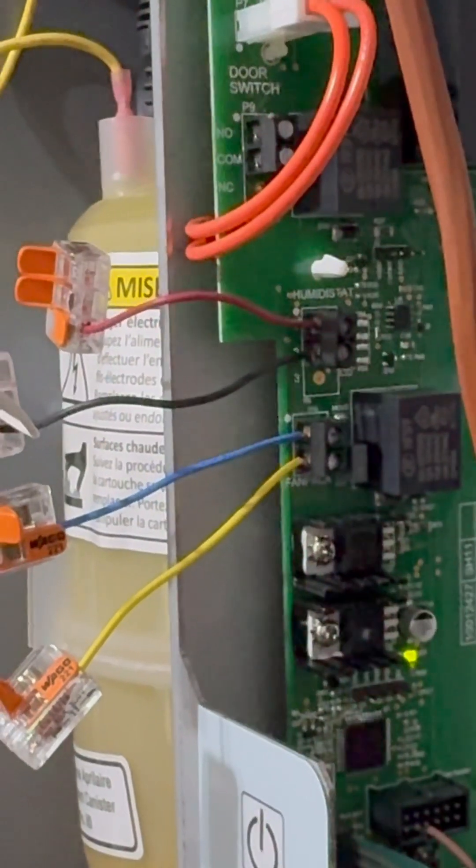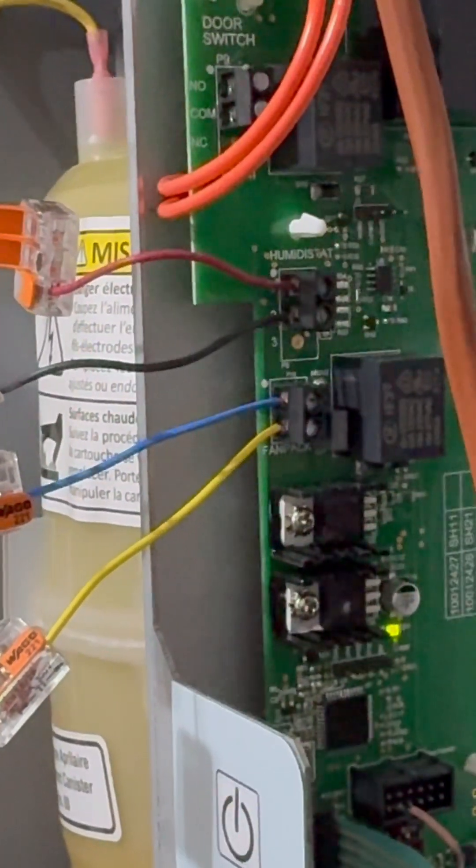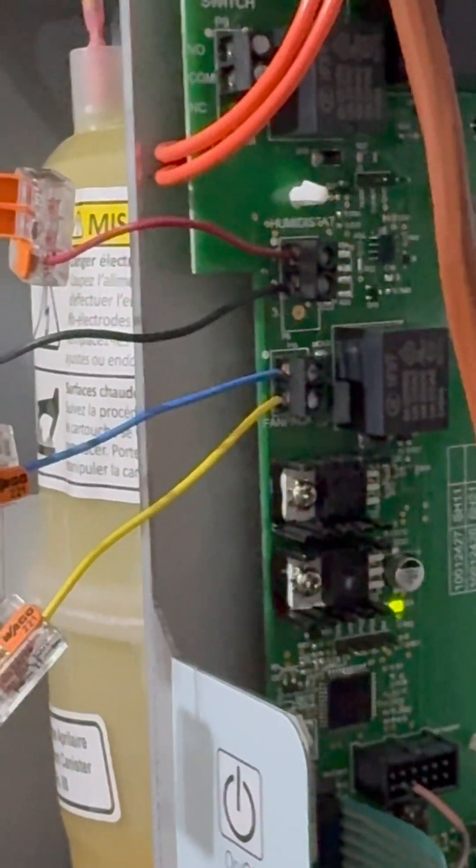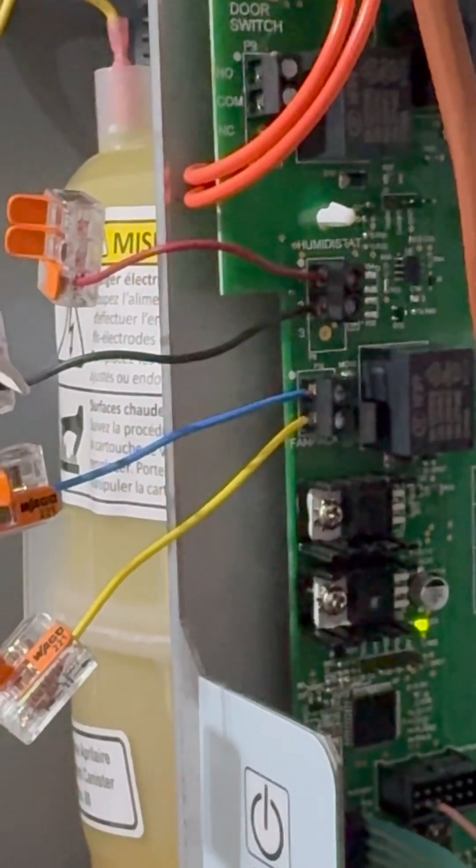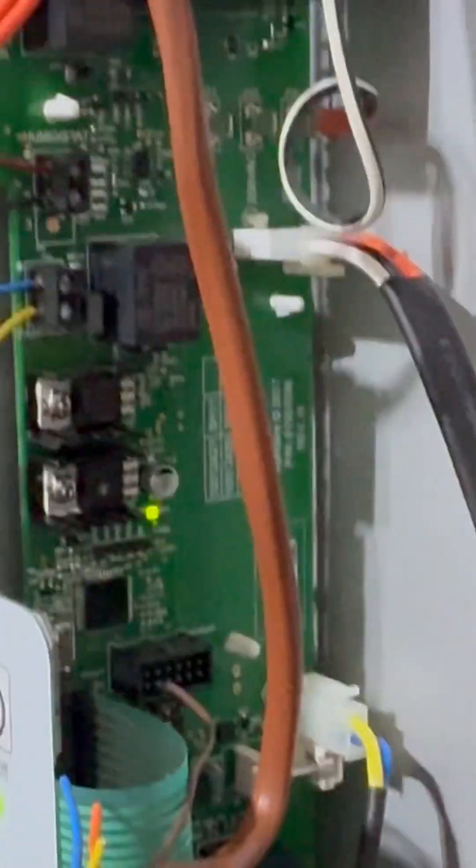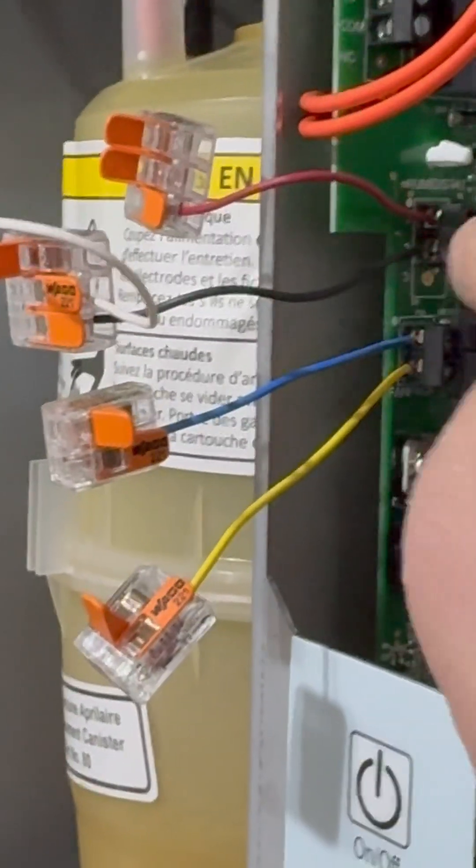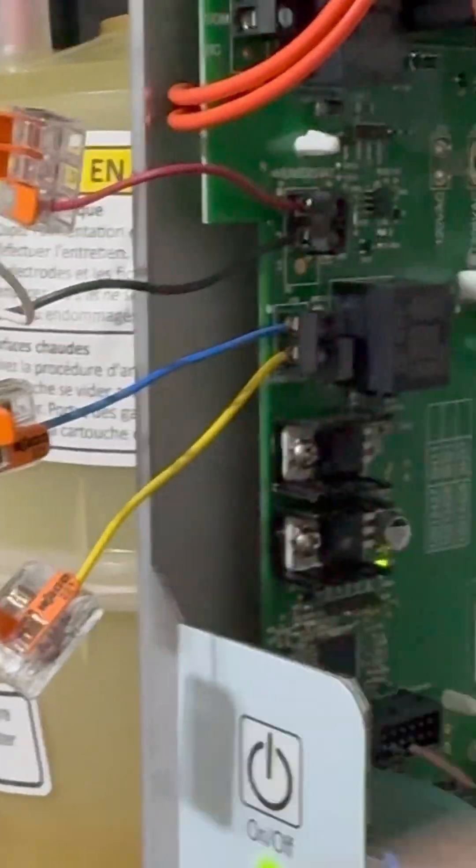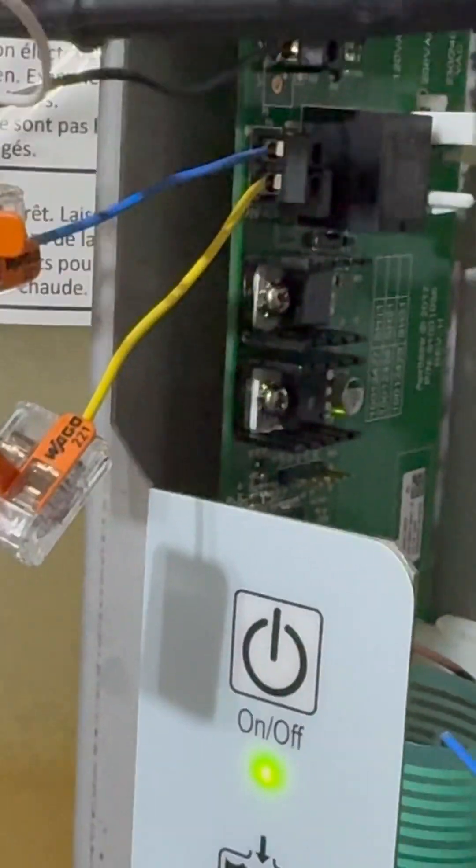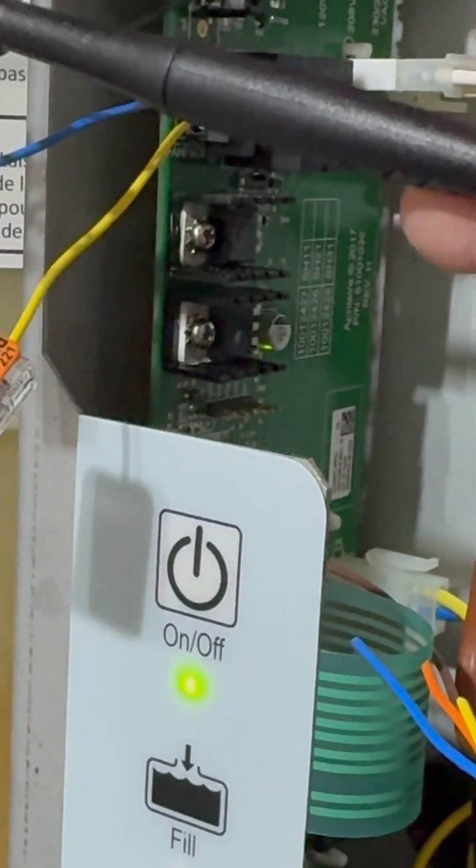The humidifier activates on a call for heating or in this case for humidification. So what I've done is I put the red lead and the black lead to the one and two terminals on the humidistat, and what I'm going to do is put in my probes here to verify that there's no voltage.